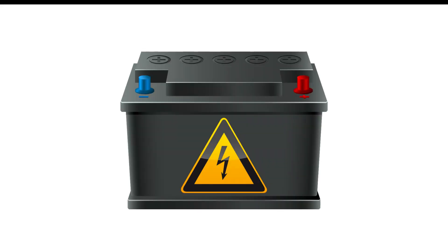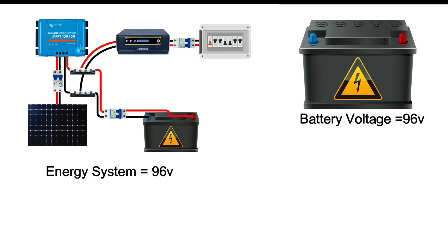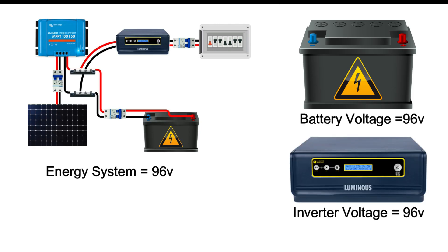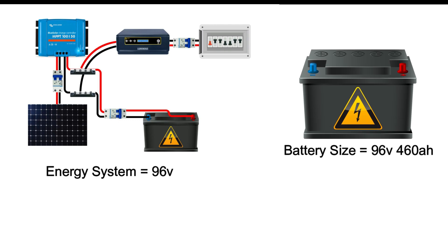Let's move on to figure out our battery size in ampere hours. For a battery the size we're considering, we will go for at least a 96-volt energy system, which means we need a 96-volt battery and a 96-volt inverter since the battery voltage must match the inverter voltage. We divide the battery capacity of 43,333 watts by 96 volts to get 451 ampere hours. Since you can't get exactly 451 Ah, you need a 96-volt, 460 ampere-hour battery to power the load on our table for the given hours and days of autonomy.